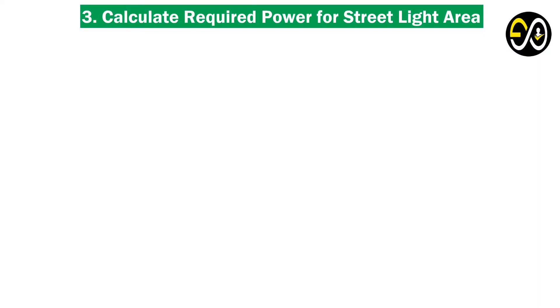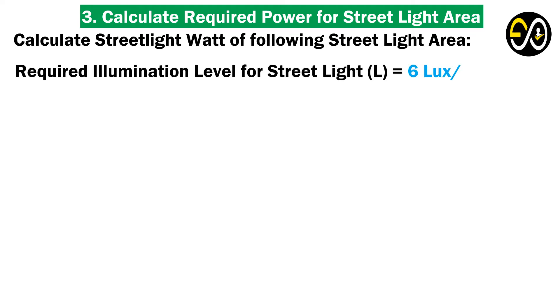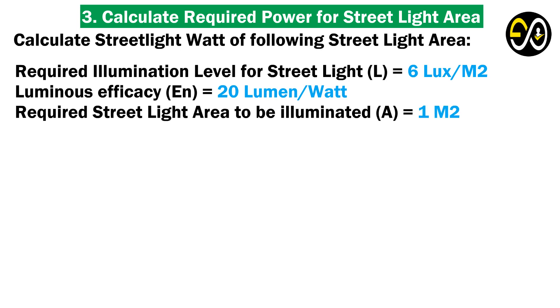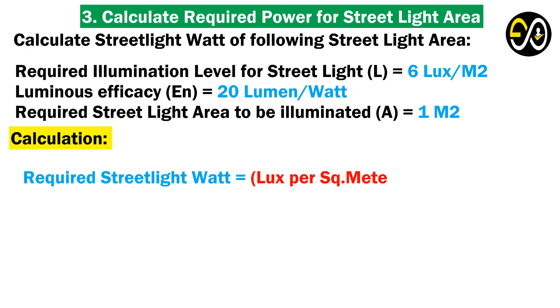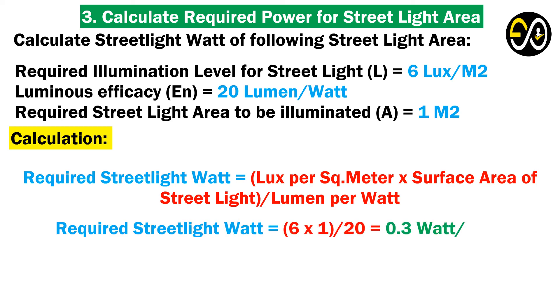Example 3: Calculate the required power for a street light area. Required illumination level for street light L equals 6 lux per square meter. Luminous efficacy equals 20 lumens per watt. Required street light area to be illuminated A equals 1 square meter. Calculation: Required street light watt equals lux per square meter times surface area, over lumens per watt, which equals 6 times 1, over 20, equals 0.3 watts per square meter.